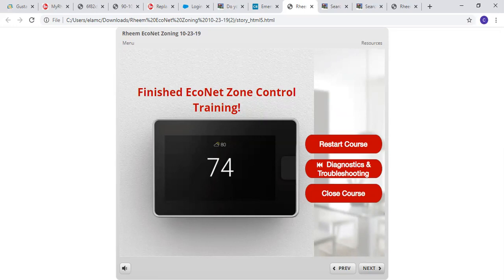That is pretty much it for the Econet zoning presentation from Rheem. Once you do one or two, it's fairly simple. 2 and 3 zones are relatively simple, because you can get away with 1 board. As you start going into the 2 boards, up to 6 zones, it's a little more intimidating, but it's not quite the end of the world. But it's a little different. But it's designed for comfort, specifically to work with the variable speed and inverter products.